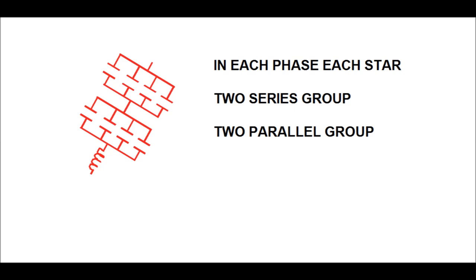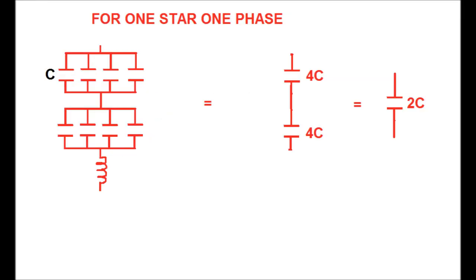Therefore in each phase in each star connection there exist eight capacitors. In total there exist 8 × 6 = 48 capacitor units in the 20 MVAR capacitor bank. Now we want to calculate the equivalent capacitance for one star, one phase, if each unit capacitor has value C.